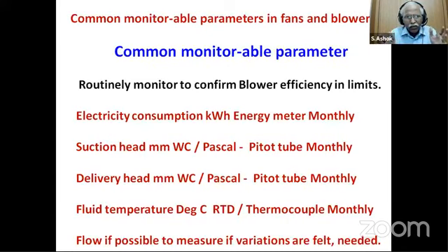The common parameter measured in fans and blowers is the input electricity consumption. The Bureau of Energy Efficiency says that for any motor above 3 HP running for 2 shifts a day, you should definitely fit a meter. It costs only about 2,000 rupees. You can fit one for any of the AHUs; it has to be fitted.